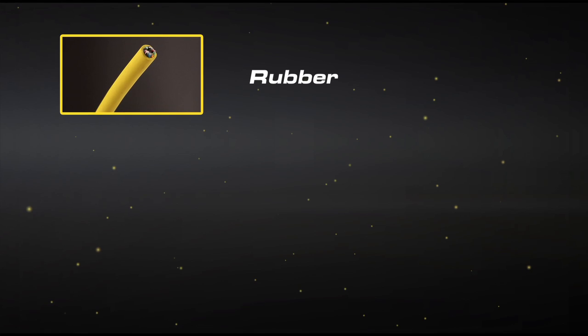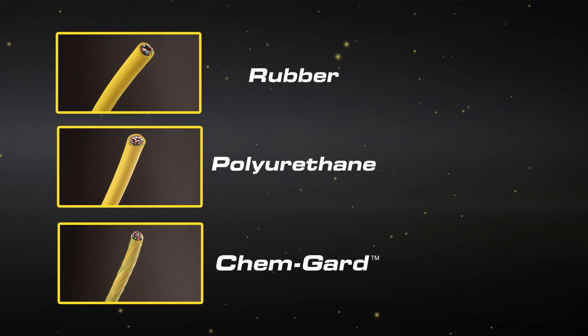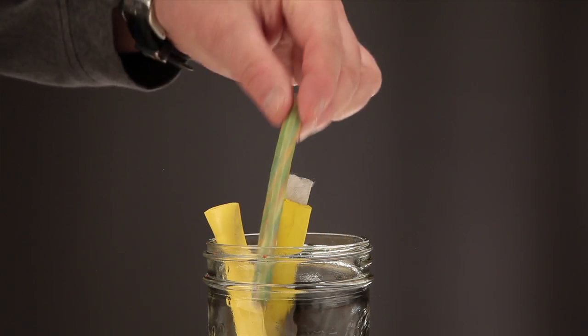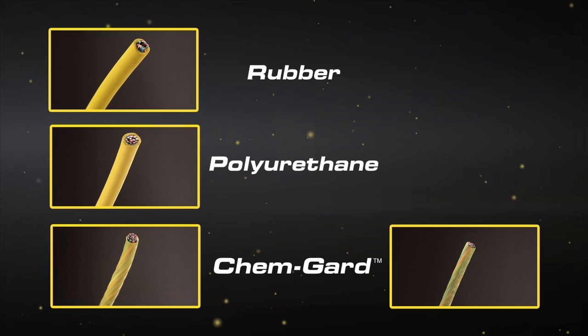Let's take a look at a rubber product, polyurethane product, and Chem-Gard before any exposure to chemicals. If you soak a Chem-Gard cable in a jar of acetone for six weeks, the jacket and insulation system isn't affected.